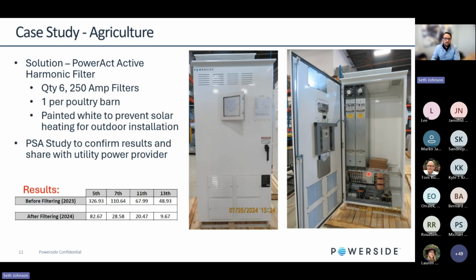So they again came to us to do another power system analysis to confirm the results that we had initially simulated for the client. And down here you can see the results. So before filtering, we had 330 amps of 5th harmonic, 110 amps of 7th, 68 amps of 11th, 49 amps of 13th. And we brought it down to this down here. So about 83 amps, 20, 29, 20, and 10 amps.